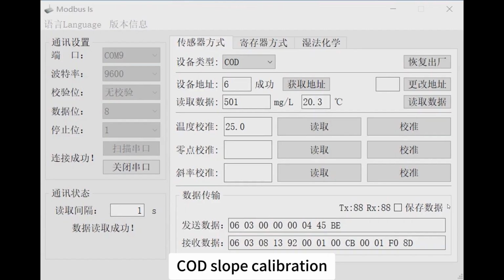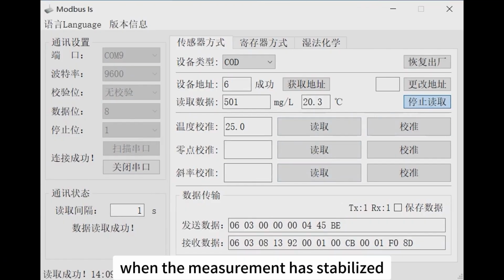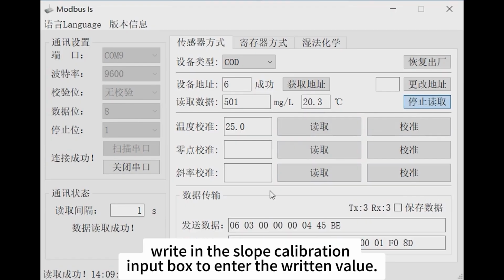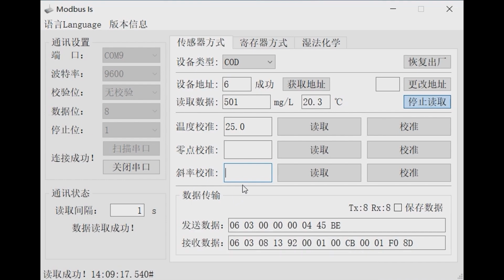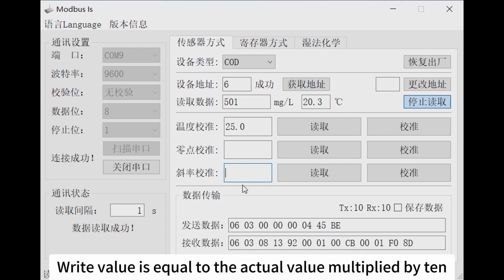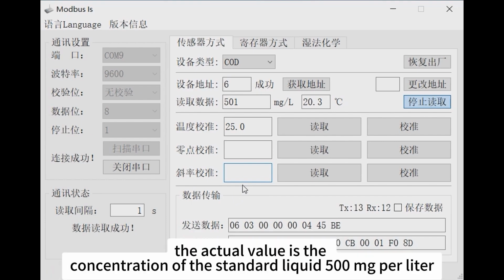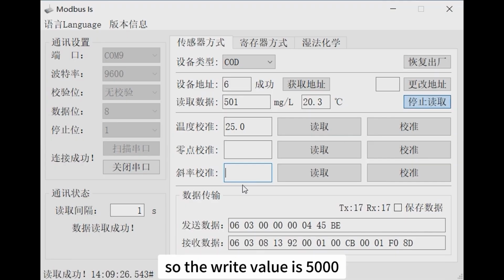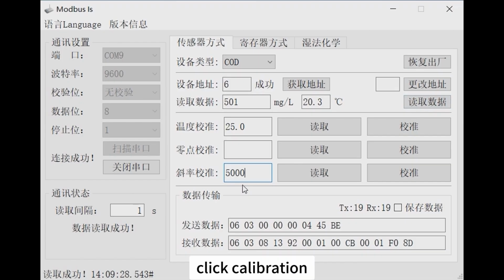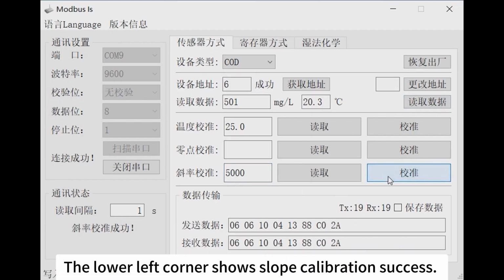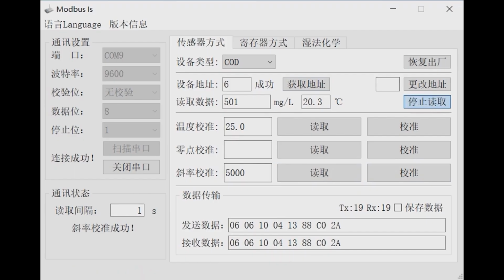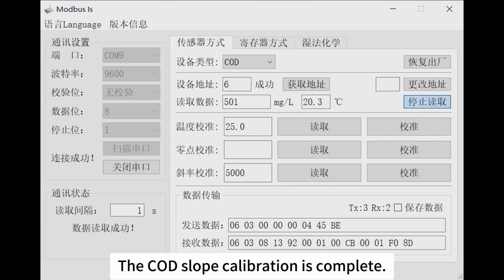COD slope calibration. Take a reading, and when the measurement has stabilized, enter the write value in the slope calibration input box. Write value is equal to the actual value multiplied by 10. The actual value is the concentration of the standard liquid, 500 mg per liter, so write the value of 5,000. Click Calibration. The lower left corner shows slope calibration success. The COD slope calibration is complete.